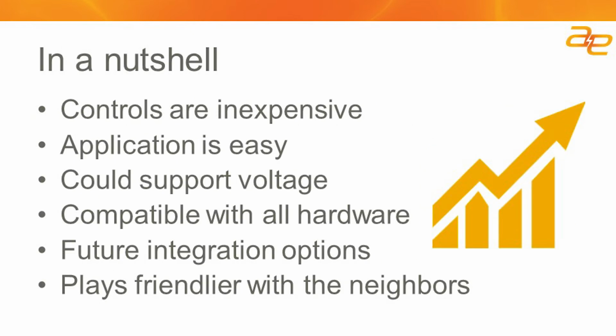So in summary, adding controls to the overall project cost of a solar site is a very small adder. It is a little bit more money, but the controls themselves are very inexpensive, and the application of just reading a meter, taking a command and distributing the commands to the devices at the site, the application itself is very easy, very straightforward. So in addition to the capabilities to do active power curtailment and ramp rate control, you have the added benefit of being able to support voltage if the utility that you're tied in with wants to do some kind of voltage or power factor support.